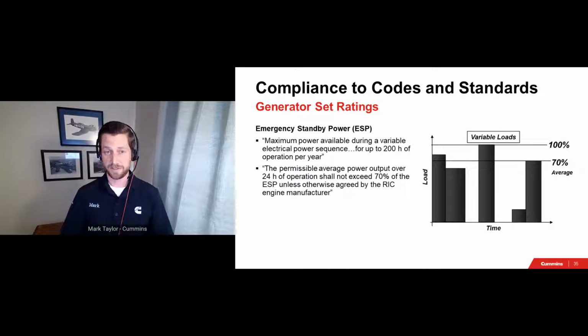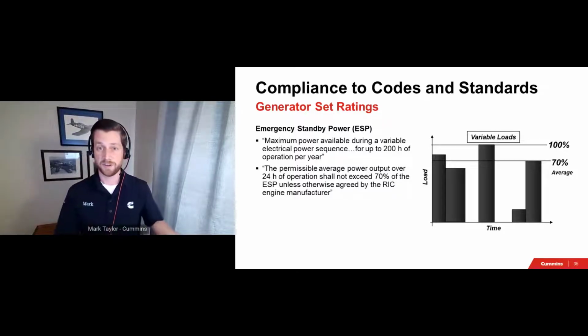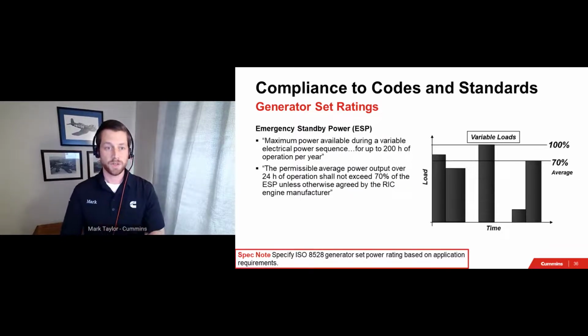Now, what ISO 8528 covers is the definition of a standby rating. It is the expected duty cycle and usage. Standby generator sets are typically used to back up a primary source of power. So the expectation is that the number of hours of runtime is generally low and that the loads are variable. Guidance on load factor over time is also called out. ISO 8528 is a reference standard, and every reputable manufacturer of generator sets should be designing their products to at least meet these standards. So continue to call it out in your specifications. There's nothing wrong with that, but just let it be known that ISO 8528 standby does not exclude gas or diesel one way or the other.